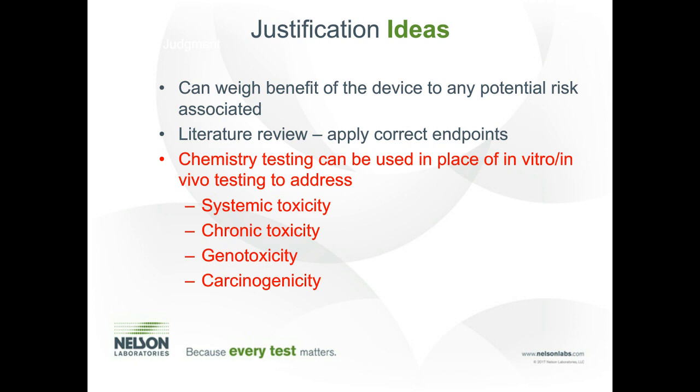When you're looking at changes of medical devices, chemistry becomes a very key player in that change because we have an initial evaluation of the chemical toxicity of an initial device, and now we have a change that we can evaluate the difference between those chemical profiles of the original and the changed one to really evaluate the impact of that change. The materials and the residuals, all that plays into a possible change much easier than a brand new device. But with a brand new device, the FDA in this document is allowing us to use extractables and leachables, if performed correctly, in place of systemic toxicity, chronic, which is also systemic toxicity, genotoxicity, and carcinogenicity.